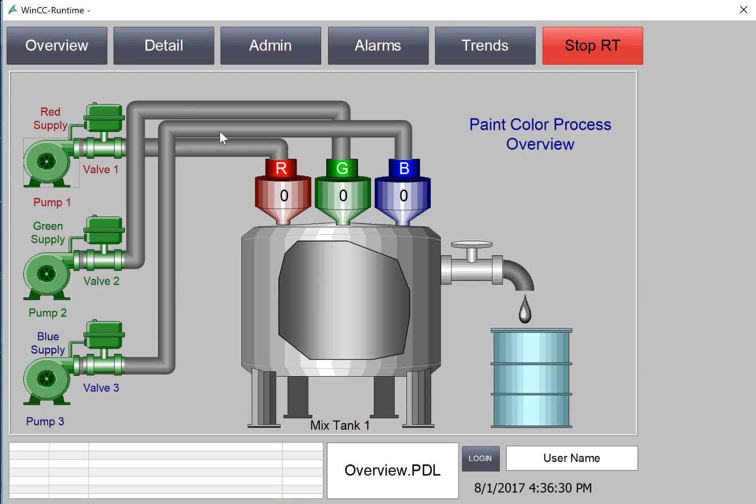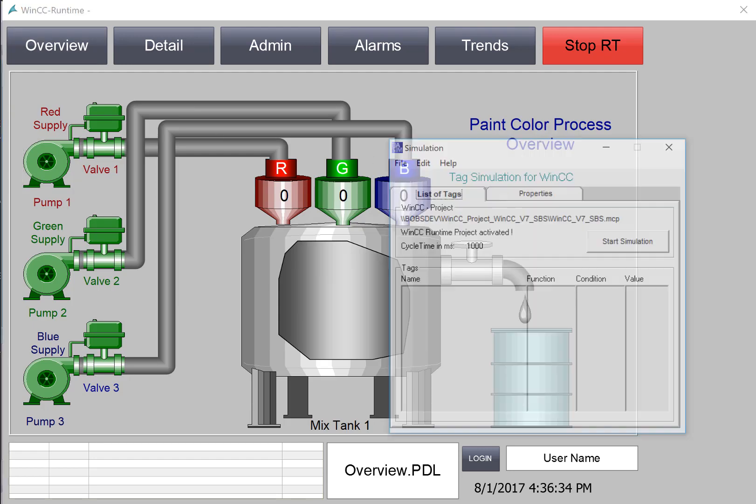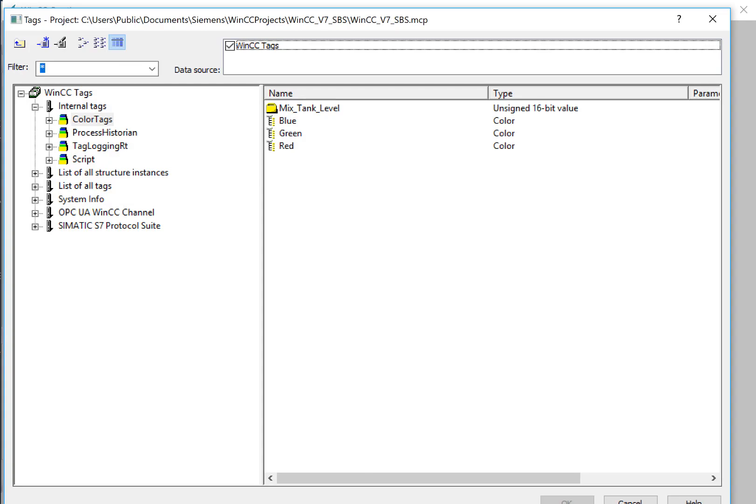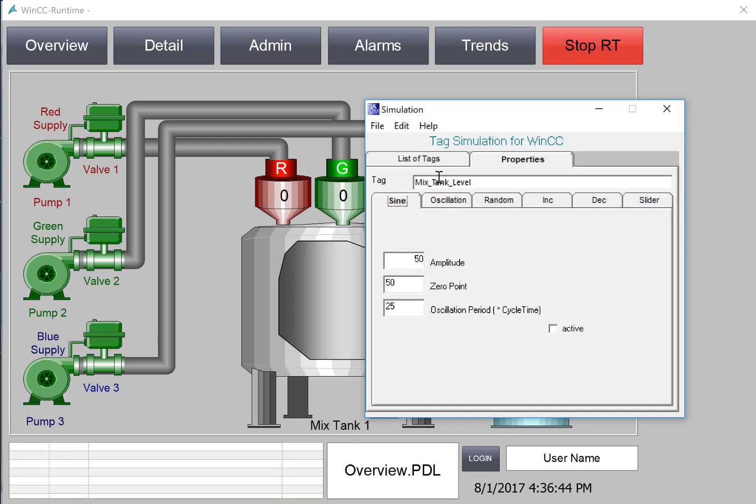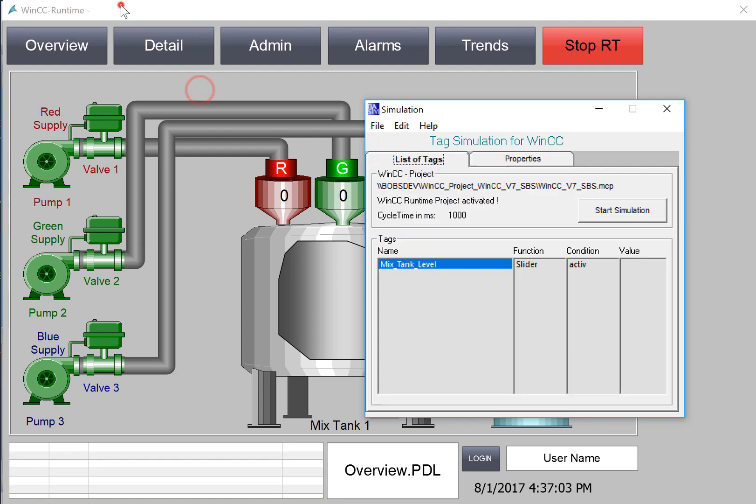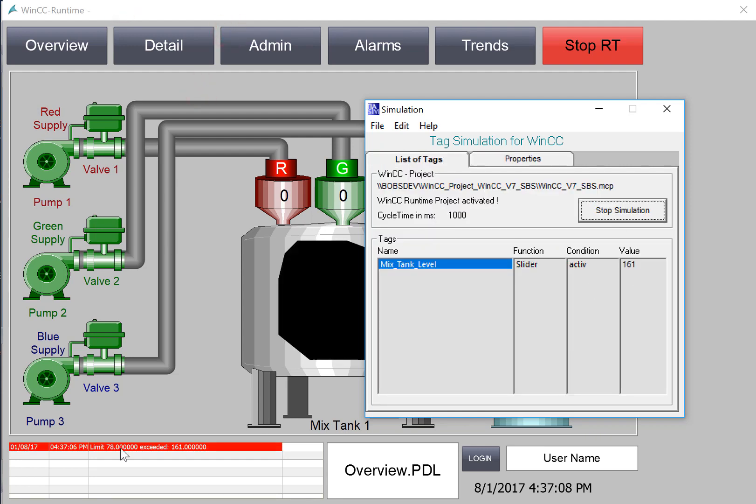So now let's test our analog alarm. I'm going to bring up my simulator. And I'm just going to add a new tag. And I'll select the mixed tank level and go to Slider. I'll give it a value above the alarm set point, which was 78, and just click Active. And then I'll hit Start Simulation. And it sets it to 161.